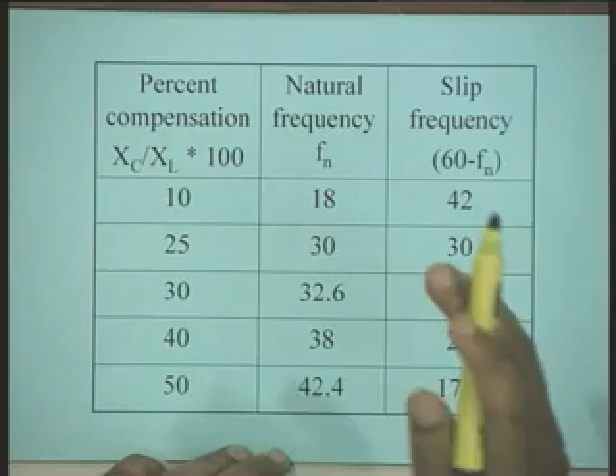With this compensation, the natural frequency of oscillation comes out to be 18 hertz, 30 hertz, 32.6 hertz, 38 and 42.4 hertz. While the slip frequency we saw as 60 minus Fn, right, because when the currents of this natural frequency flow in the stator winding, then the torque developed will have a frequency of 60 minus Fn, that is the slip frequency. Slip frequency torques are produced, and this slip frequency torque should not coincide with the frequency of any of the torsional modes. This is one of the important requirements.